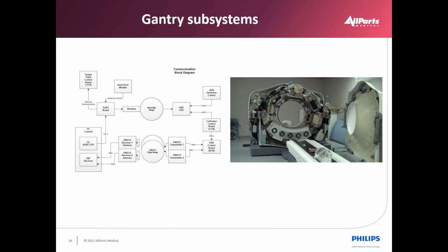So once the DAS collects the data on a per view basis, it will transmit. In this case, 32 rows go on one channel and then 32 rows go on the other channel over the slip rings, through our communication rings, to the receivers, which then wind up in the DIP, aka the DAS interface processor.